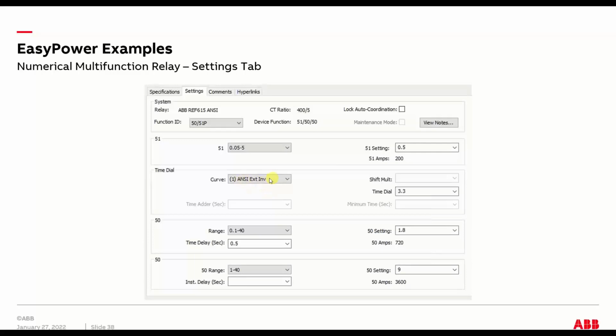This is where you pick the curve. Now, when you select this for this specific relay, you're going to get a whole list of curves. So I just selected the ANSI extremely inverse on this relay. Time dial setting, range. This is for your instantaneous protection. This 50 here is for your time delayed version of it, because you have a time delay plus a tap setting. And then this 50 here is for your instantaneous. So you actually have essentially a long time, short time, and then a true instantaneous setting all on this relay.